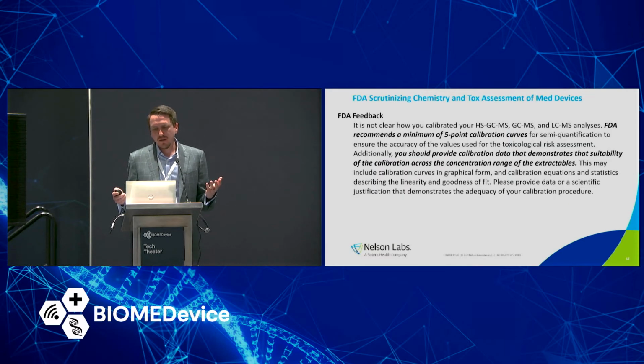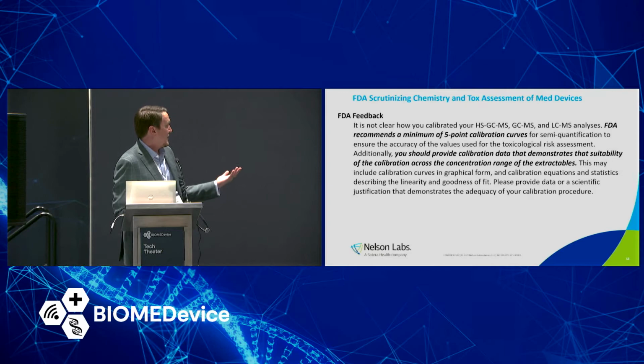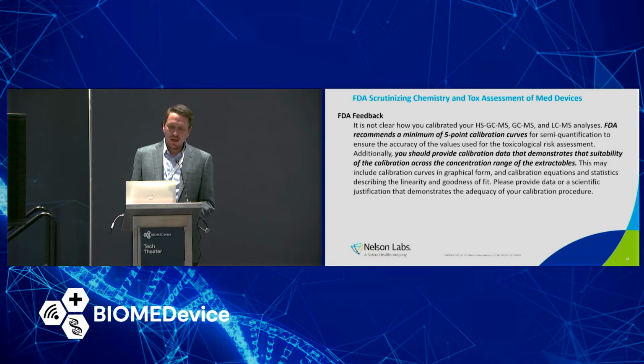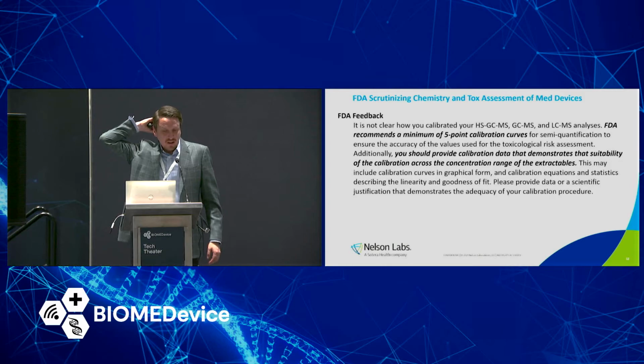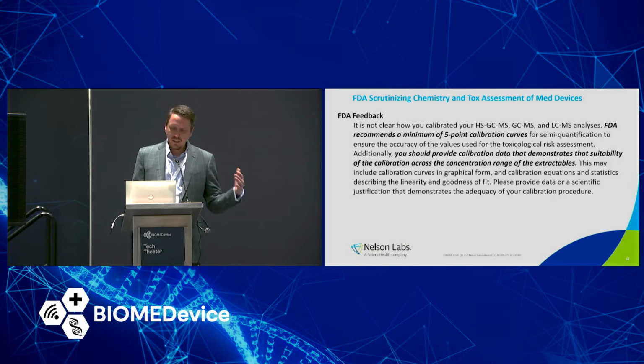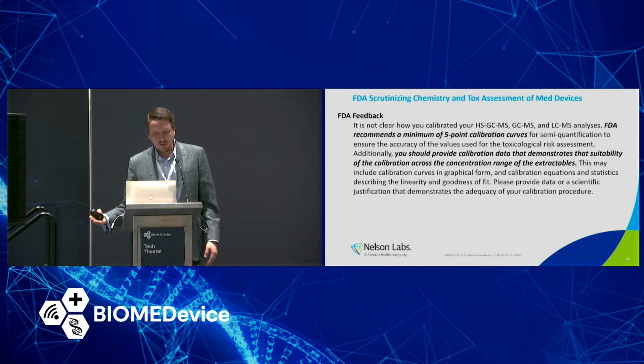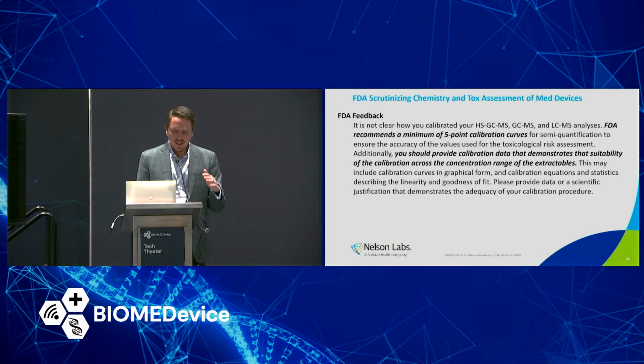Okay, so here's a more or less random grab bag of FDA feedback on E&L studies that I pulled quickly. This one is interesting, right? It says it's not clear how you calibrated your GC instrumentation. The FDA recommends a minimum of 5-point calibration curves for semi-quantitation. You should provide calibration data that demonstrates suitability of the calibration curve across a concentration range of extractables. You can see there they talk about linearity, goodness of fit, all of this stuff. So this is something that we've seen more and more. It's really a lot of work to supply this information to the FDA.